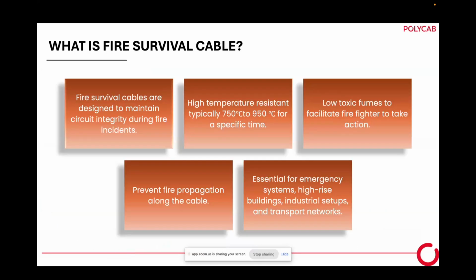Now what is fire survival cable? Fire survival cables are designed to maintain circuit integrity during fire incidents, with high temperature resistance — material that can bear up to 950 degrees for up to 3 hours. Beyond that we cannot guarantee, but in our in-house testing, some cables withstand up to 3.5 hours. This depends on the quality of raw material we use.